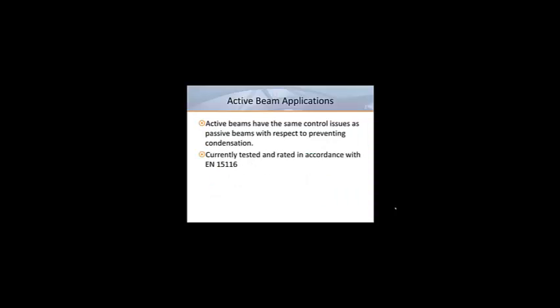Whether it's a passive or an active beam, the same care must be taken to ensure that the control system is able to closely monitor supply water temperatures and indoor environmental conditions to prevent the accidental formation of condensation. You should also be aware that new industry standards are being developed for chilled beams. Active beams are currently tested and rated in accordance with the European standard EN 15116. ASHRAE is currently developing standard 200 as a method of test for active beams and AHRI is developing standard 1240 for the performance rating and certification of beams. These standards will probably be adopted within the next calendar year.